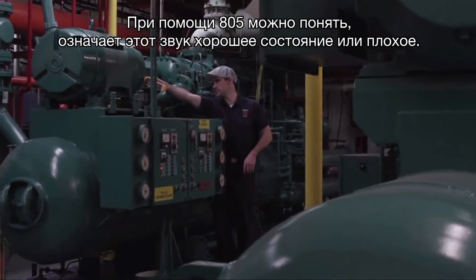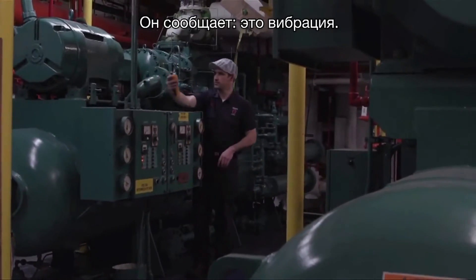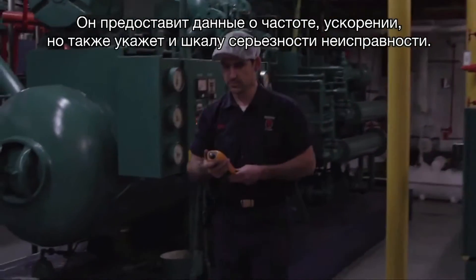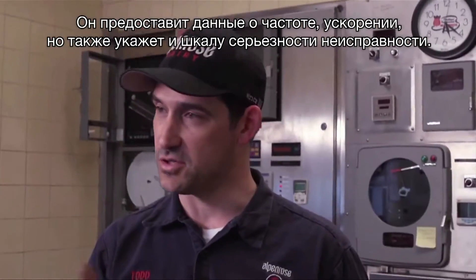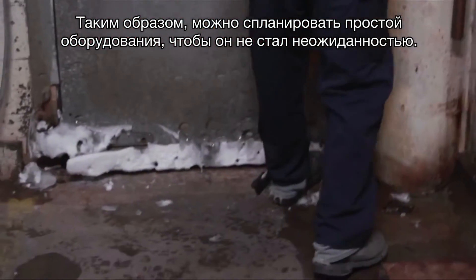You'll be able to find out with the 805 if it is good or bad. It tells you the vibration — it gives you a readout for velocity, acceleration, but it'll also give you your severity scale. It's going to tell you it's good or needs attention, so you can schedule your downtime and avoid unscheduled downtime.